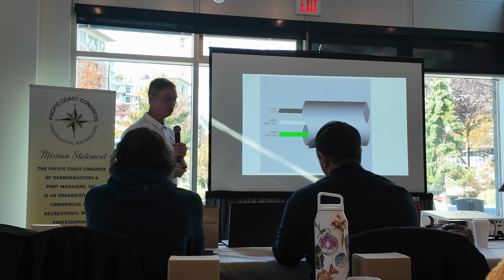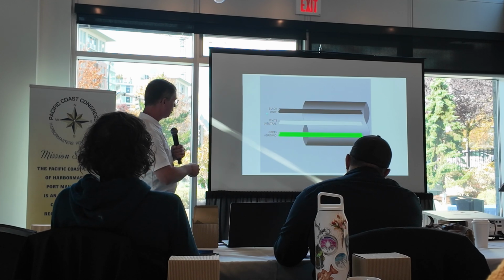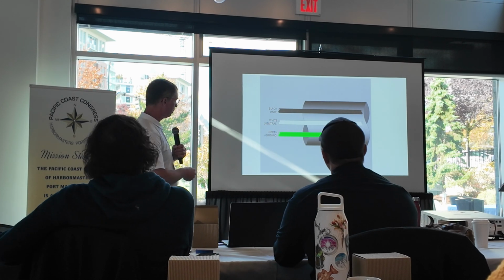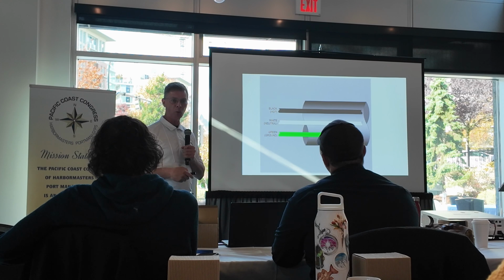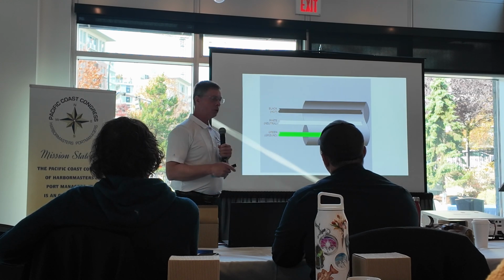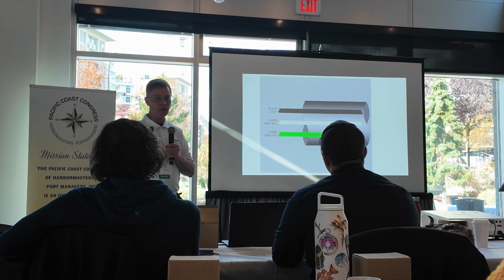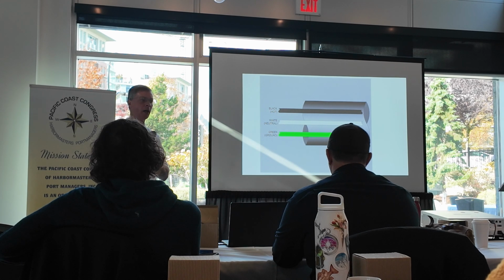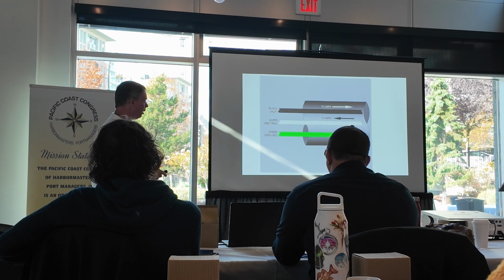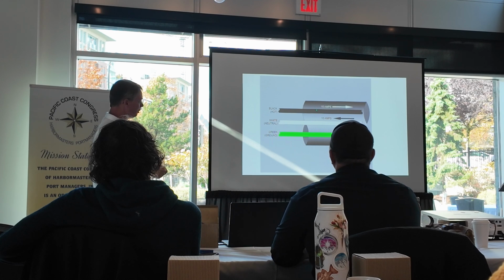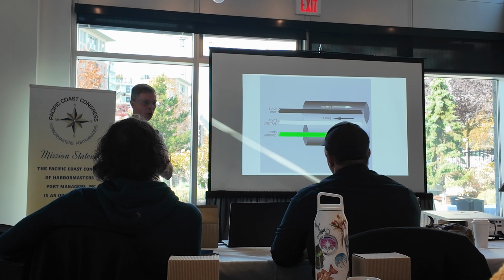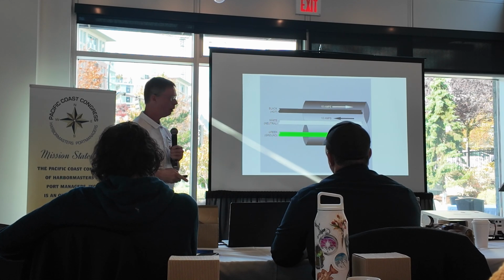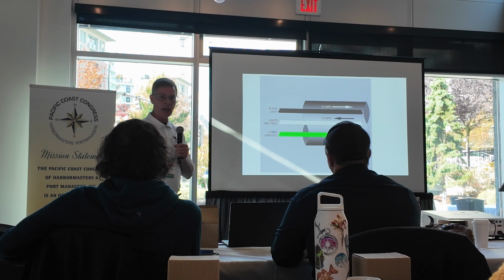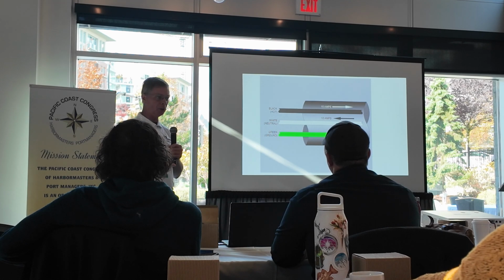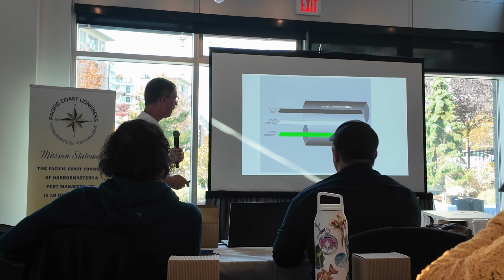So graphically, I'm going to open this table up. You got the hot, the neutral, which is the return, and the green, which is the ground. Okay, everybody understand where we are? It can be very technical, but I'm going to try to make it very, very simple for everybody in this entire class to understand AC leakage currents. If you look at this, you got 10 amps going to the boat, and where would the 10 amps come back? Down the neutral. And this is a balanced system, right? Okay, so that's very good. On a 30 amp, it's not overloaded, it's perfect. You got 10 amps going to the boat, 10 amps coming back.